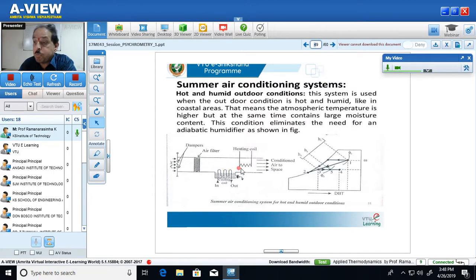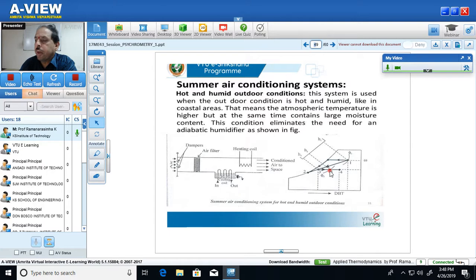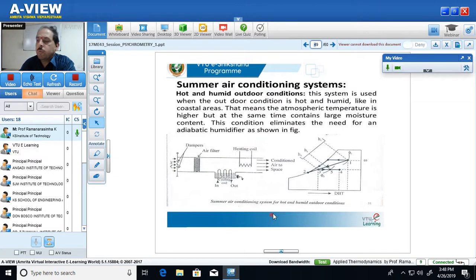Since a certain amount of air is bypassed without passing through the cooling coil or heating coil, that is why theoretically air should come out of the cooling coil at point 2, but instead it comes out at point 3. Similarly, instead of coming out of the heating coil at point 4, it comes out at point 5. This is the working principle of the summer air conditioning system for hot and wet or humid weather.